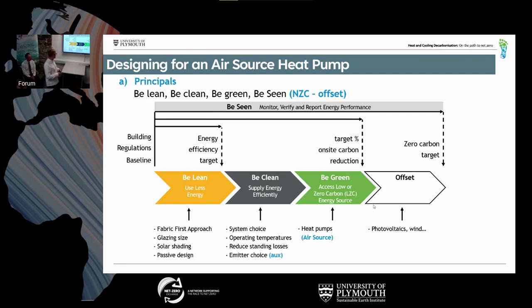The next one is operating temperatures. You've probably heard everyone saying the same message, but heat pumps really like low temperatures. What compromises that is domestic hot water - Ross was talking about that before. As soon as you get into storing hot water, you have to maintain a certain temperature, 60 plus degrees in a cylinder, and heat pumps don't particularly like that. You can get high temperature heat pumps, but the coefficient of performance is around potentially 200%, so it really limits the options there.